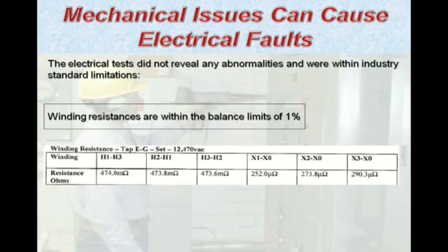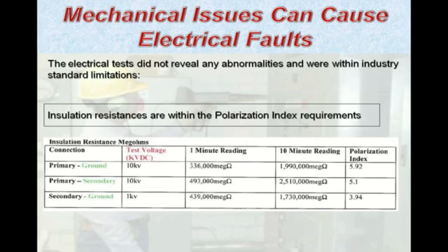Shown here are the winding resistance measurements. They're all within 1% of each other, which is acceptable. The insulation resistance, or what some people call megger, is shown with what's called the polarization index. This test is done by applying a test voltage for 10 minutes and then recording a 1-minute value and taking the 10-minute value that's measured, dividing it by the 1 minute, and that gives you what's called your polarization index. Typically, we like to see this well above 1, and as you can see by the results, the lowest PI value is nearly 4. So the insulation at this point is pretty good.